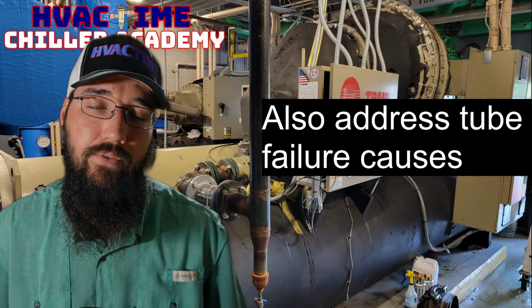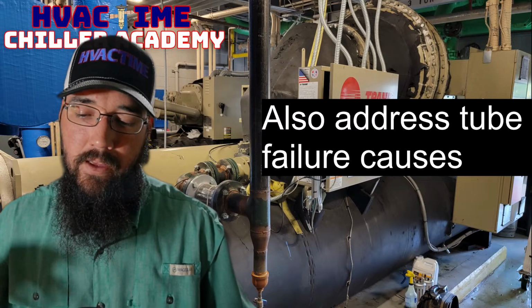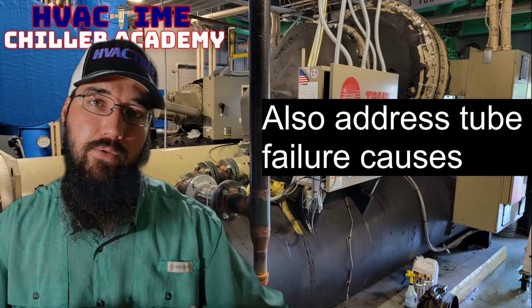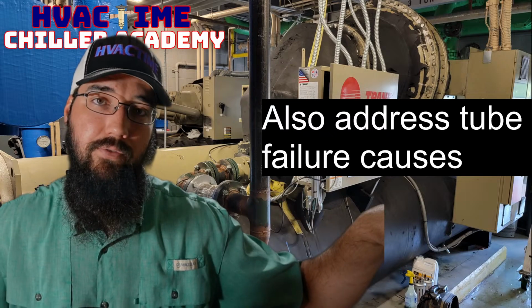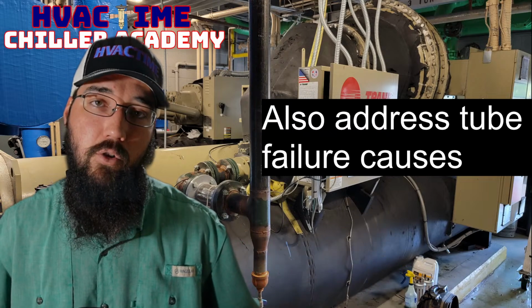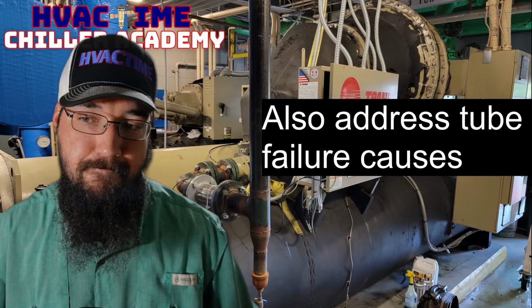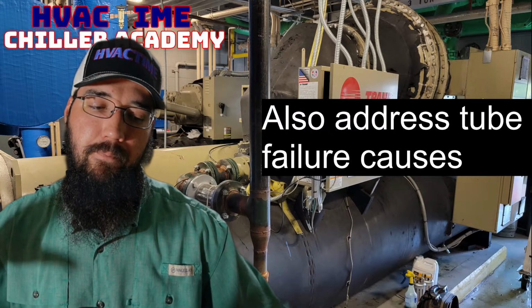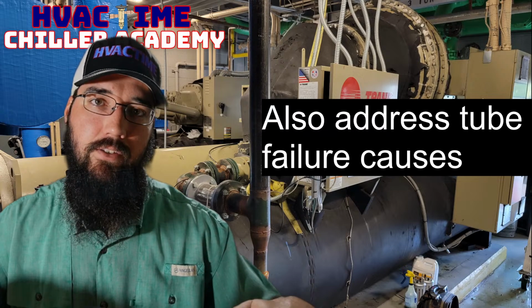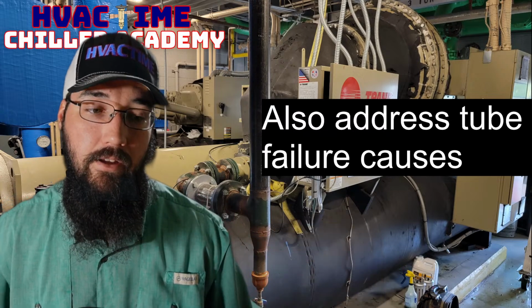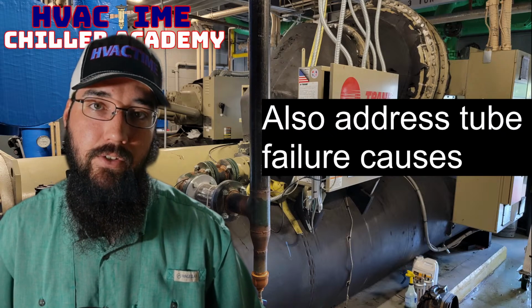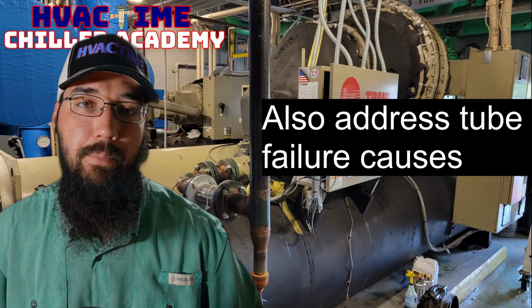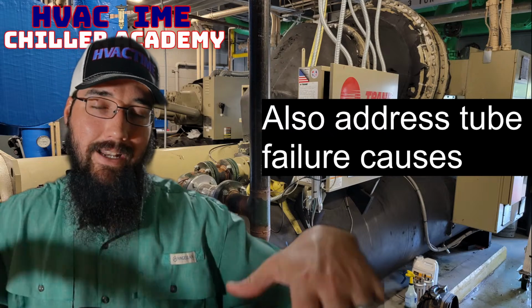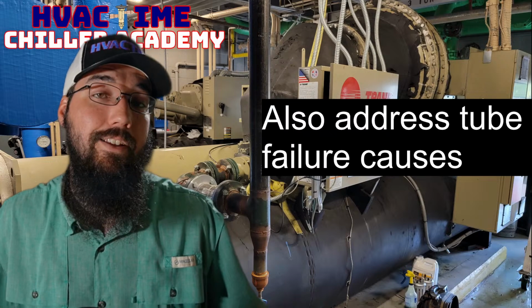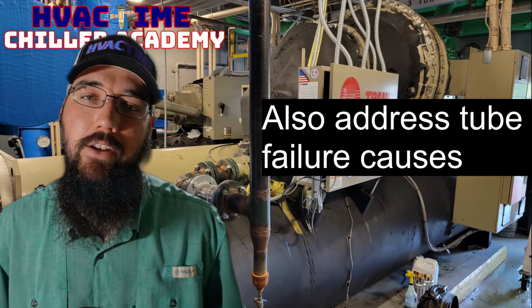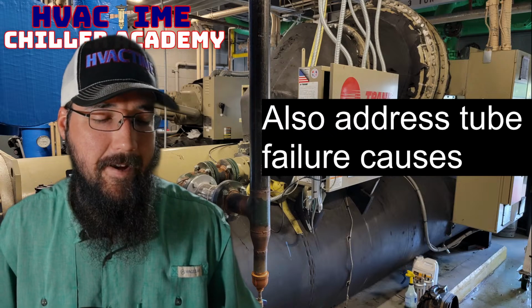Now, if you had a catastrophic failure, which I've seen some of these where it literally floods the chiller. First of all, the refrigerant, if it's a high pressure machine, is going to flow out into the water circuit. But on a low pressure machine, water's just coming straight in. In a catastrophic event that I've literally seen, I've had pictures sent to me of CVHs where the water level was up into the suction nose cone, just at how much had filled up in the chiller and then set there on top of that. So that would be catastrophic - that'd be the definition of catastrophic.